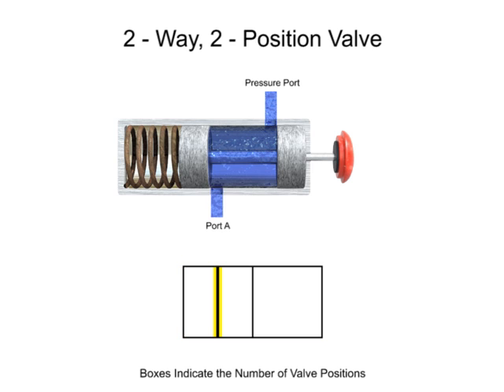Continuous lines are used to indicate fluid flow between ports. For complex valves, the ports may also be labeled. The input port is typically labeled P for pressure. Outlet ports are typically given alpha characters starting with A. Other times, the letter stands for the destination of the fluid. For instance, the letter T would indicate a port that is connected to a tank. This is a fairly simple valve, so port labels are not required.